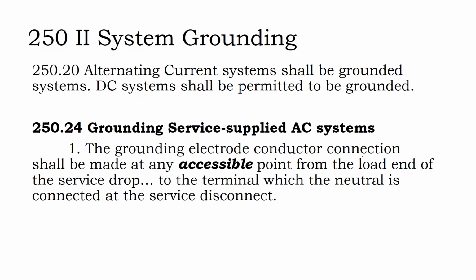Let's see, we have AC systems are grounded. DC systems shall be permitted to be grounded, but they don't necessarily have to be grounded. The DC side could be completely isolated from the AC side, and then you just need that positive-negative reference. But that still doesn't mean you don't have to ground the metal parts that are not part of the DC power system, that are not intended to be current carrying parts, but they're still metal parts exposed to current up on the rooftop. Just because you have a DC system that is ungrounded, that's more of an energy processing term for the inverter; it doesn't get you out of your system grounding requirements.